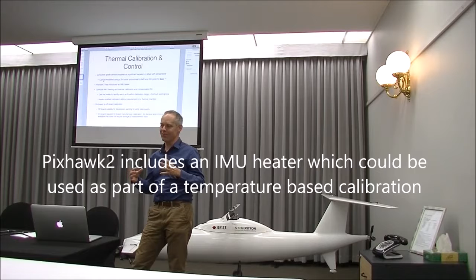Not necessarily to do barometers, it's a bit hard to get that stable pressure environment, but we have the ingredients now to cold soak a board, turn it on, and then have it automatically just linearly ramp the temperature up over a linear range. We can have a linear set point raising temperature, so we don't have all our samples in one part of the temperature range, so it's all distributed.